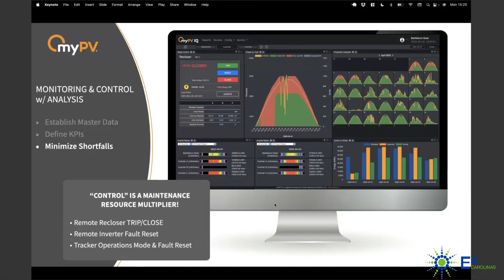And then there are trackers. Trackers are also probably one of the most mechanical portions of a solar site these days, sometimes with hundreds of motors. All of those motors and batteries and wireless comms cards can have failures, and they do. So when trackers are not operating properly, the ability to change their mode from wash or stow mode, or the ability to reset a fault, is terribly, terribly important to preserving reliability of these sites for the grid.